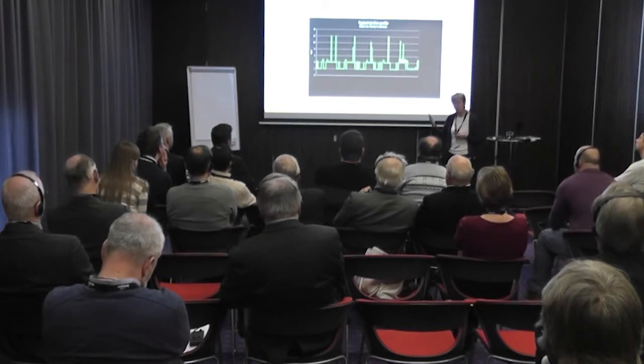In the very beginning, we tried to find out what they are doing in other countries, and we found this study from the University of California, and they show here that in the typical lab the flow profile is from 8 up to 48 cubic meter per hour and square meter. And this is quite shockingly high, going up to 48. And it's a challenge to find out what you are going to design both the local and the central units for. If you calculate all units for 48 and add this, you get 2 big central units.